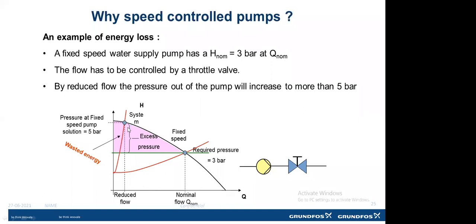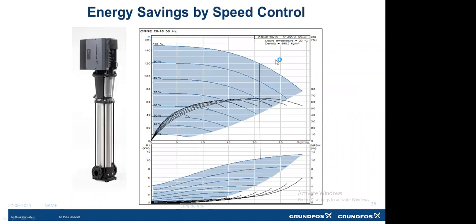So how do we save the energy? Let's say, for example, we have selected and installed one pump for a capacity of 21 meter cube per hour at 120 meters of head. At this duty point, the pump will consume 10.2 kilowatt. Let's say our requirement has reduced, and we have not installed the VFD, and we throttle the valve. We have reduced the flow to 10 meter cube per hour because our requirement has reduced from 21 to 10, and we have throttled the valve. The head will increase from 120 to 142 meters of head, and this pump will consume 7.5 kilowatt of power.